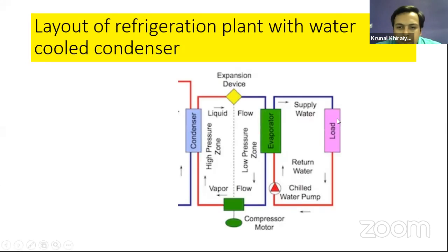Now we are going to look at the layout of a higher capacity refrigeration plant with water-cooled condensers. In this figure, the load is represented by the pink color box. We have a chilled water pump. Water is the secondary refrigerant we are using here, which transfers heat from the load to the evaporator. Our main vapor compression cycle is shown here, and the condenser is a water-cooled condenser, obviously, because our plant has a high capacity. The blue line shows water which comes in at low temperature and goes out at a high temperature from the condenser. So every time we need cold water to absorb the heat from the condenser.